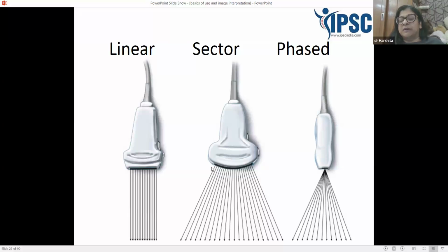This is a sectoral probe or a convex probe. What happens? The piezoelectric crystals emit the ultrasound beams and they are diverging. Can you see them diverging? This is used to scan deeper areas. Why? Because here you can see the ultrasound beam is getting diverted, and when it comes to the lower end of the screen, it can get reflected and you can see more area of the screen.